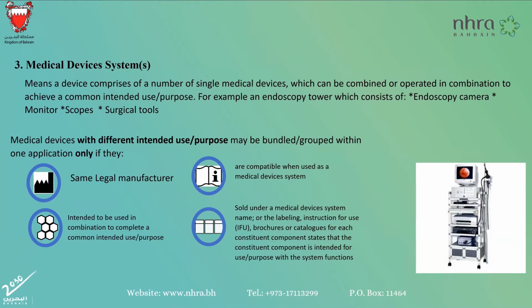An example to this bundling group would be the endoscopy tower, as it consists of a number of medical devices, such as the endoscope camera, the scopes, the surgical tools, monitor, the trolley, and other components. So as you can see, each component separately has a different intended use, and some components wouldn't actually be able to operate separately.